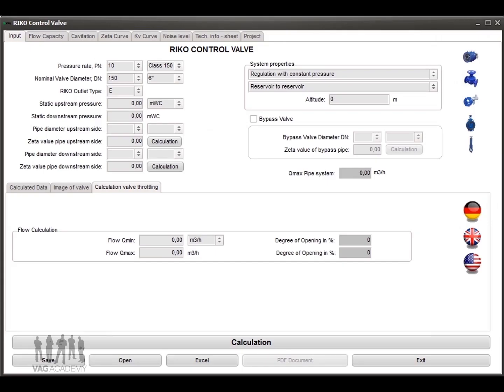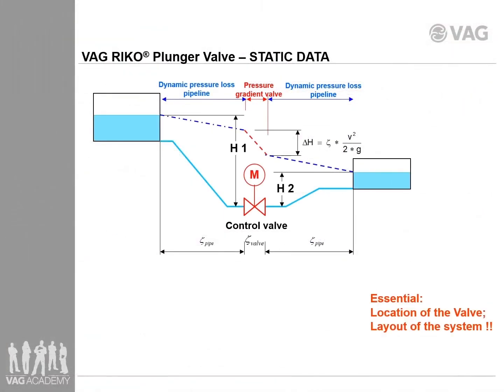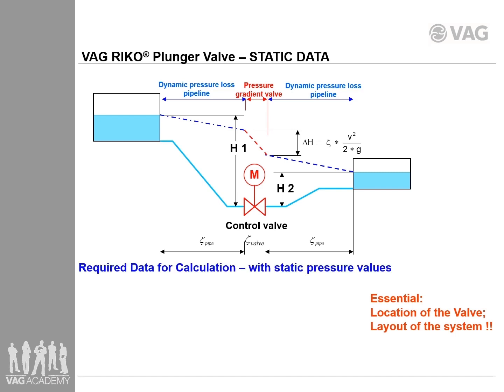In the next screen you enter all the required hydraulic data from your project. For this calculation VAG uses only static pressure values, not dynamic values. I will show this towards the end of the video. The required static data is shown in this chart. For the upstream side of the valve you need the static upstream pressure, H1.